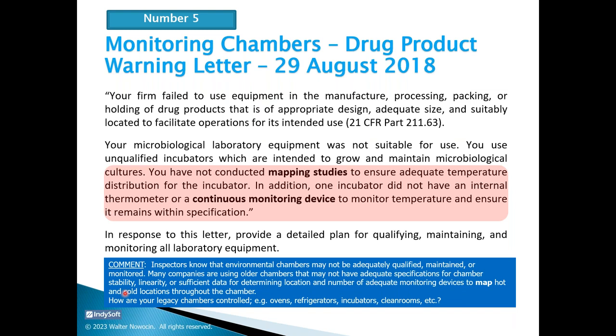Number five, monitoring chambers. So here we have a microbiology laboratory using equipment that's not suitable because the incubators are unqualified, which are intended to grow and maintain microbiological cultures. You have not conducted mapping studies to ensure adequate temperature distribution for the incubator. In addition, one incubator did not have an internal thermometer or continuous monitoring device to monitor temperature and ensure it remains within specification. Now look what the expectation is.